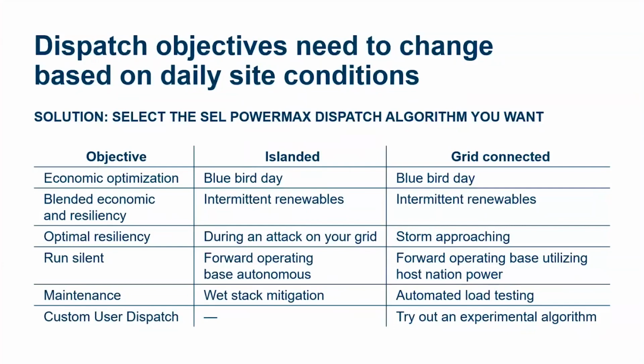For example, if you have a storm approaching, you may wish to go what some people call storm mode. We call grid-connected optimal resiliency. Here in this table, it's a selection. It's a table. And the user can select this with our PowerMax solution. But then the storm goes away. It's a bluebird day. Go back to economic optimization. So you can't achieve optimal resiliency and optimal economic at the same time. Repeat that to yourself multiple times. It can't be done. But you can select one mode or the other, or a blended mode. And that's what this table shows you. Up to and including even maintenance mode. You may choose as your maintenance cycle to automatically load test your generators. Let the PowerMax microgrid controller do that for you.